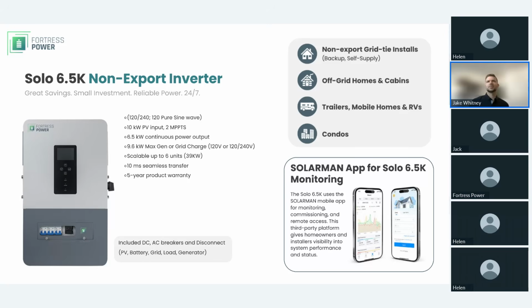Now, why is this product needed? Well, one, a lot of systems that are off grid or grid tied, they need something small. They just want simplicity of a backup, regardless if it's a small cabin, a couple of lights, or just a water pump for agricultural purposes. This will be perfect. So this one is a 10 kilowatt PV input, 2 MPPTs. It is 6.5 kilowatt continuous power, 9.6 kilowatt max gen or grid charge. You can scale up to 6 of these units.